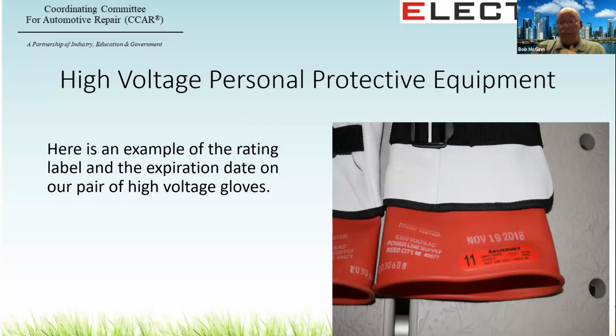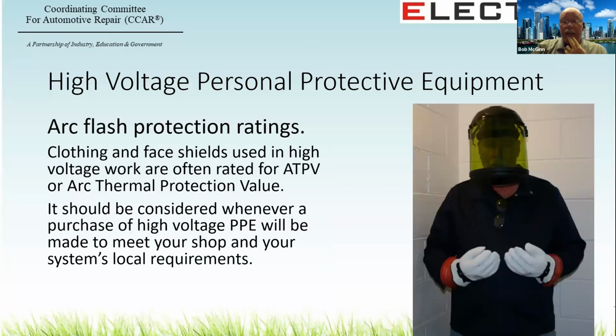If I was giving this presentation in person, I'd have samples of PPE to pass out among the group. Unfortunately, the photo examples will have to suffice. Here is an example of the rating label and the expiration on our pair of high voltage. And now would be a good time to discuss PPE that has an arc thermal protection value rating, or ATPV. These devices are essential for thermal isolation, not necessarily electrical isolation. You need the right arc thermal protection value for your process and your application.